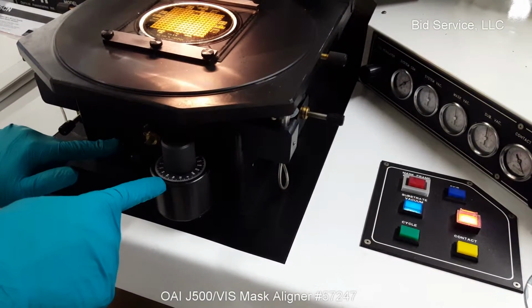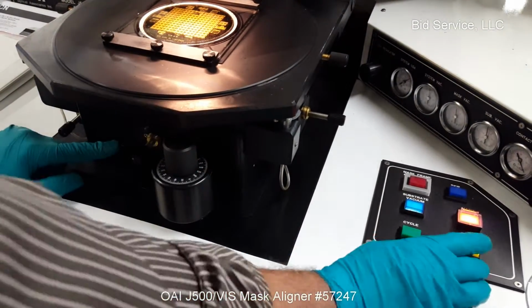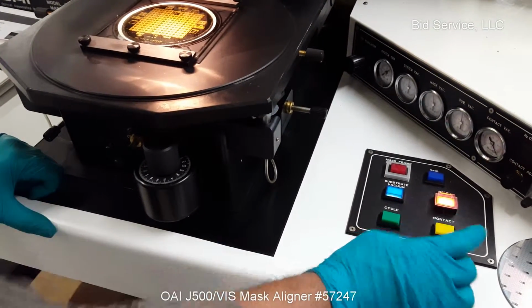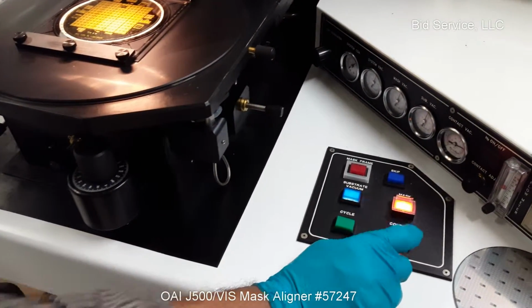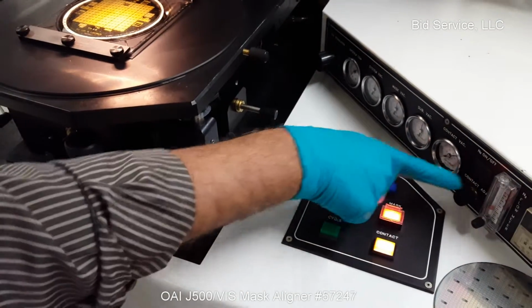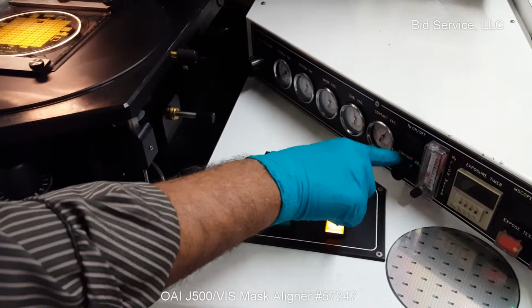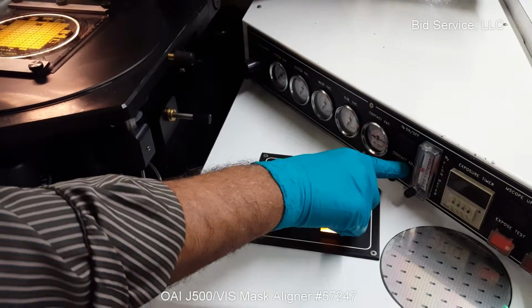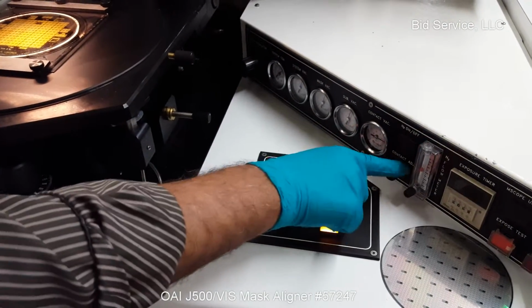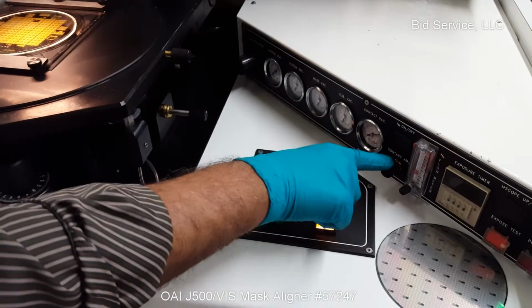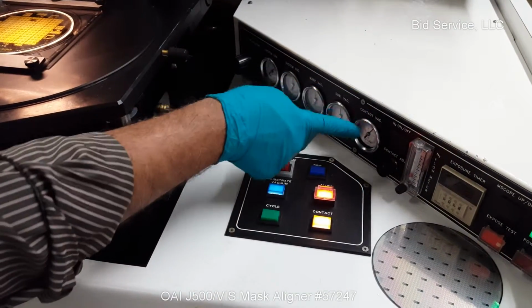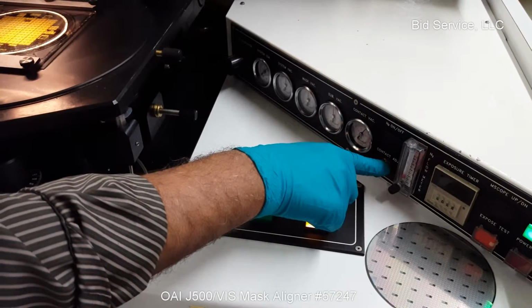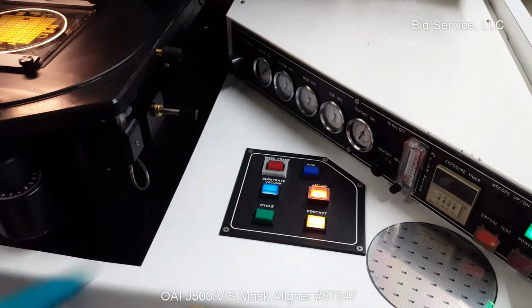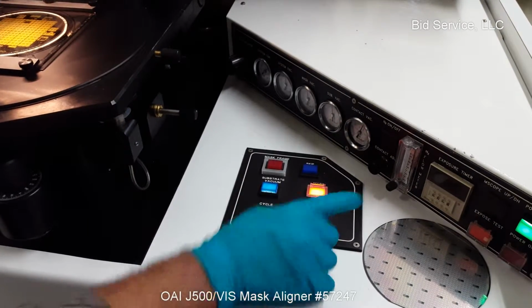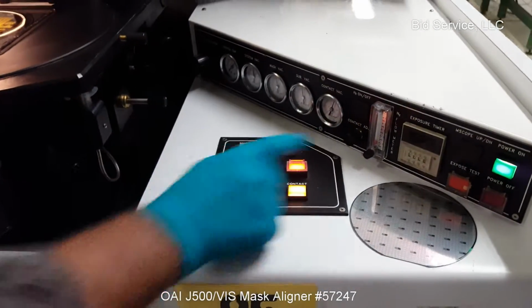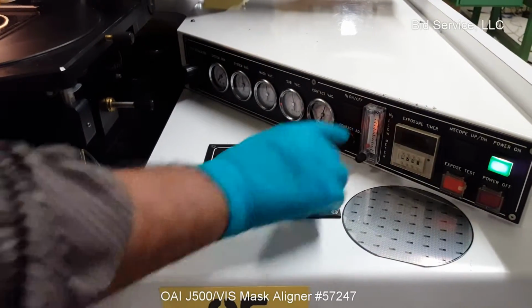So it's at about 50 microns here. The chuck is lower, and if necessary, you can turn on the contact vacuum and try to adjust the contact. Typically, it is normally operated between 5 to 7 inches of mercury. For hard contact, turn the knob clockwise and the contact vacuum level will increase to 10 to 12 inches. Now when the vacuum increases, the nitrogen flow will go down.